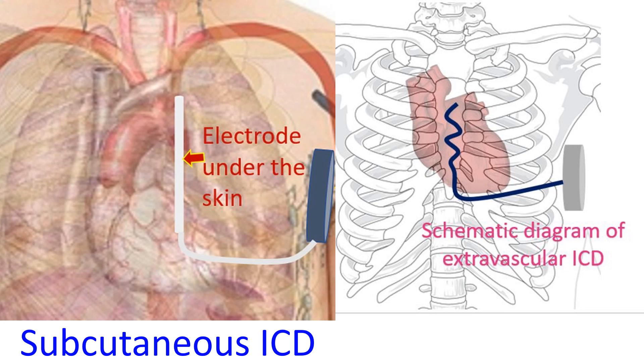These new types of ICDs have been innovated to avoid potential problems with intravascular leads in conventional ICD systems. Intravascular leads can get infected, fractured, or dislodged, and occasionally perforate the cardiac chambers. Leads can also lead to formation of intravascular thrombi and cause thromboembolism or venous obstruction. For these reasons, the lead has been called the Achilles heel of most cardiac implantable electronic devices, which include pacemakers and ICDs.